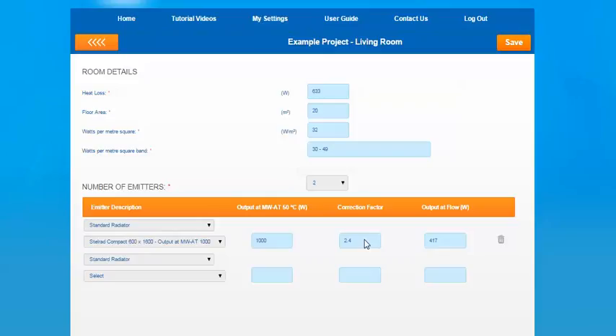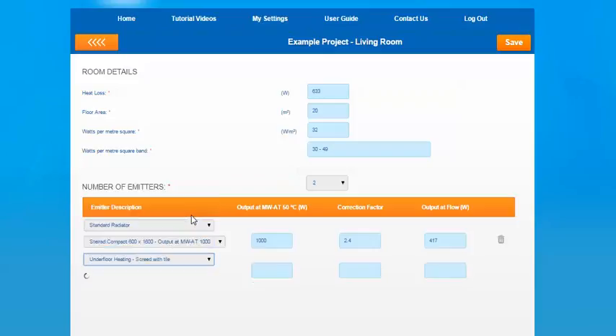In this section, you can also select underfloor heating as an emitter. The process for this is slightly different. You're not required to add in the output on this as it's not a requirement for underfloor heating. If you add a new inventory item for underfloor, you're just required to add a description. This is basically the manufacturer, type of pipe and the pipe spacing that will be applied. The pipe spacing should be based on the heat emitter guide and the guidance given within that document.